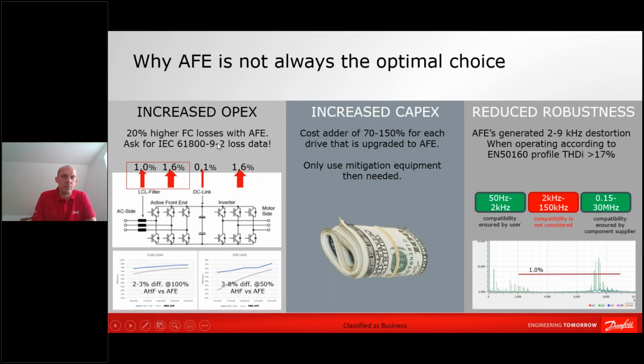First of all, if you look at the losses for an active front-end drive, you will see that the front-end part adds significant losses to your system. So when you look at a loss ratio of your drive, you can see that 1.6% of the losses is coming from the motor side. You have 0.1% coming from the DC link. And now when you add switching devices on your input side, you have added another 1.6% of losses, plus the losses of the LCL circuitry in front of the drive. And now you end up with losses somewhere around 4-5% of your installation. And when you're running a pump or a fan that runs 24/7, these extra 2-3% of losses that you have added to the system simply means that you will have a very high energy bill each and every month due to the more losses that you have generated.